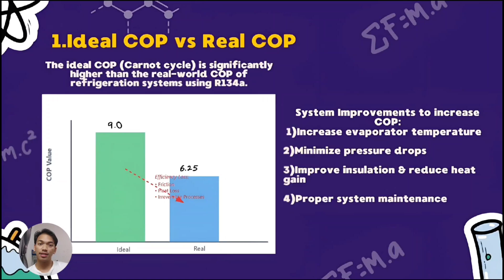But system improvements alone aren't enough. We also need to address refrigerant selection, and this is where things get complicated. This table reveals the central challenge: sustainability and safety are often in tension with each other. Take R744 or CO2. It's environmentally excellent, natural, non-toxic, and has minimal global warming impact, but it requires extremely high pressure systems, which means higher equipment costs and more complex engineering requirements.